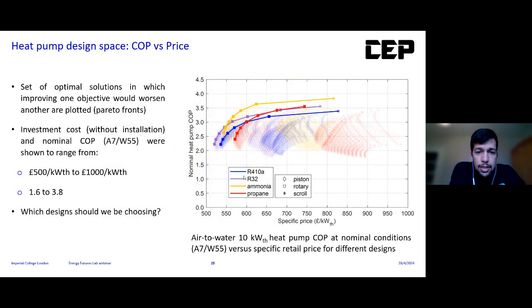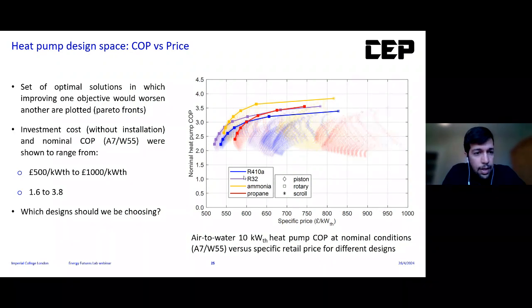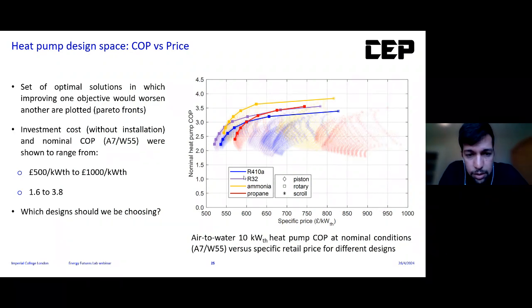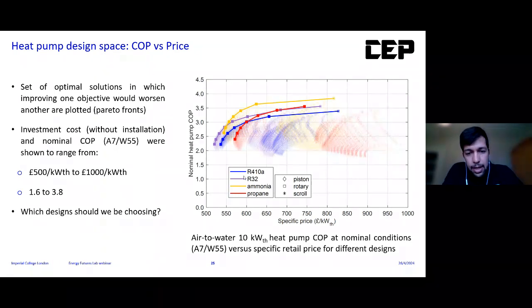So in this figure now, we look at the whole design space of different heat pumps. We can see the nominal heat pump COP as a function of the heat pump price. And you can actually see that for many different fluids, different compressor and heat exchanger sizes, there is a large change in the specific price.